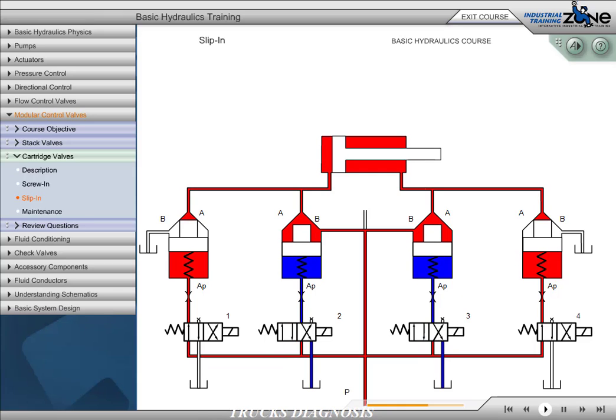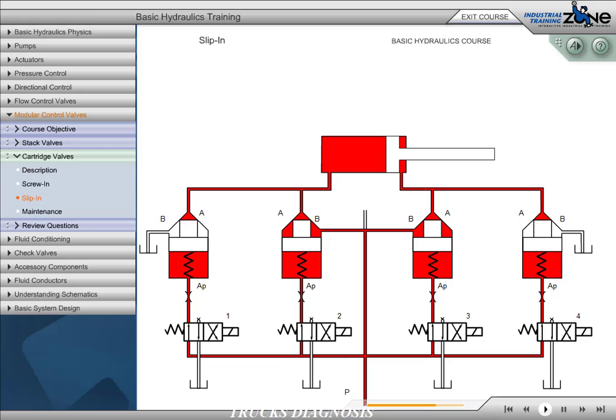Energizing valves 2 and 3 will create what is called a regenerative circuit, which will cause an increase in the cylinder extend rate. Flow is from port P to port A, with the return flow from port B combining with the flow going to port A. With all four valves de-energized, the cylinder will be held in the position where it stopped. Pressure from the A port of each directional control valve holds the respective cartridge valve closed, blocking both the A and B ports of each cartridge valve. Since they are check valves, they have zero leakage, so there will be no cylinder drift.